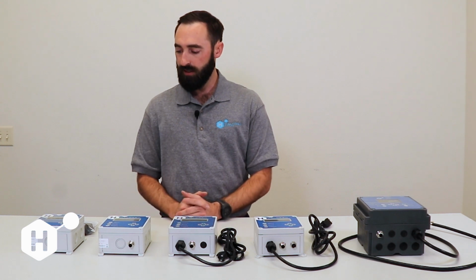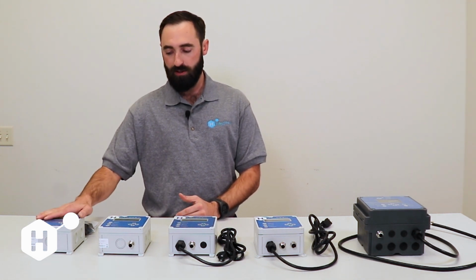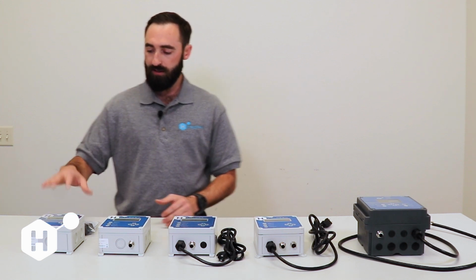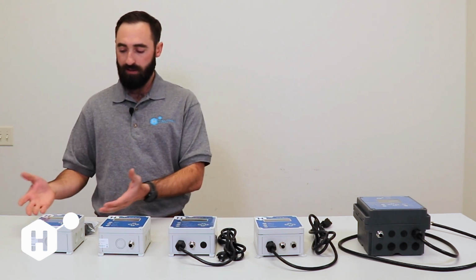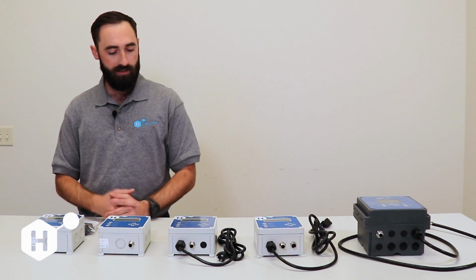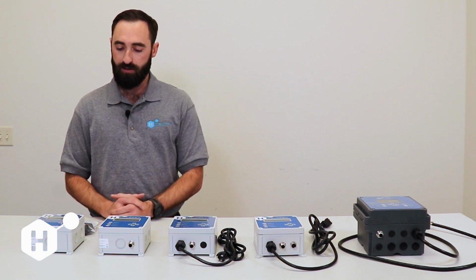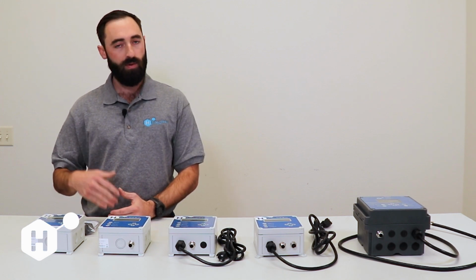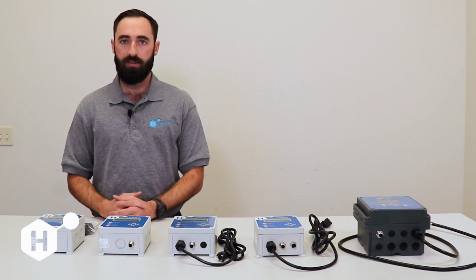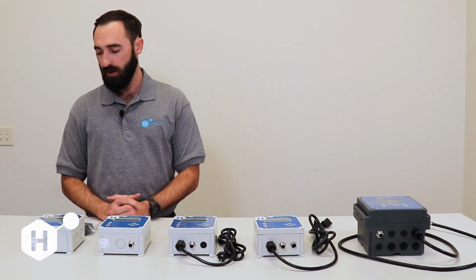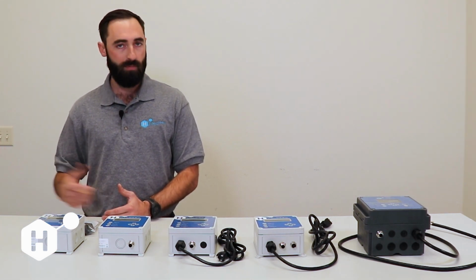So the first one that we're going to dig into is our D01 display. This is a display transmitter that needs external power supplied. Basically, the entire point of our displays is to give a way of reading our sensor measurements and communicating with either a PLC, a SCADA system, or pushing on our signal over Modbus.